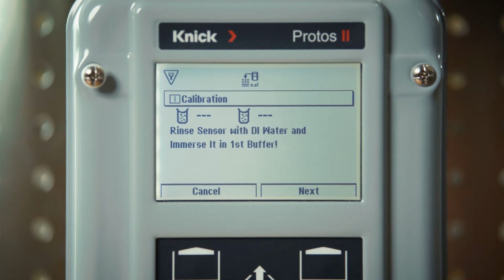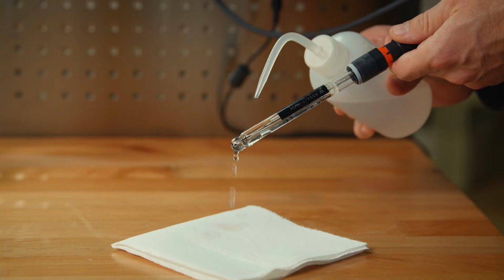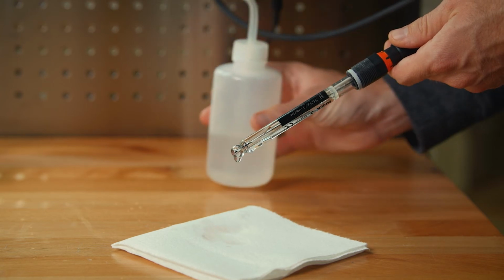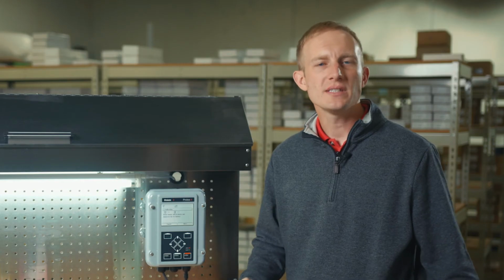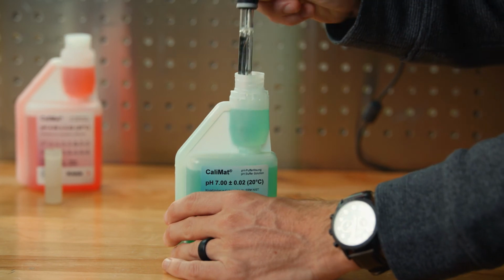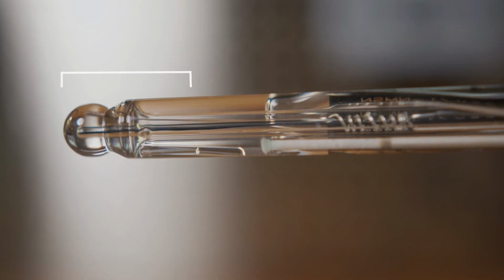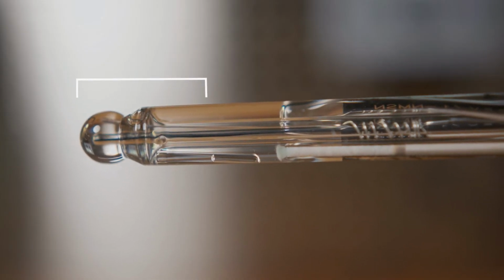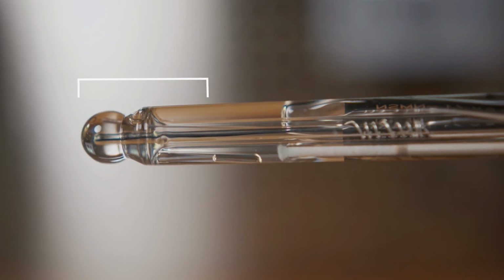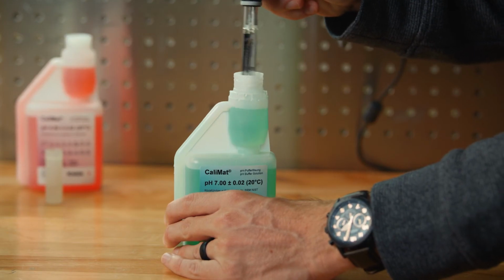Here, we are prompted to rinse the sensor with DI water and immerse it in the first buffer solution. We will do so and place the sensor into the buffer 7. Please ensure that the entire pH measuring bulb, along with the sensor's junction, are immersed in the buffer. Stir lightly and then press the Next button.